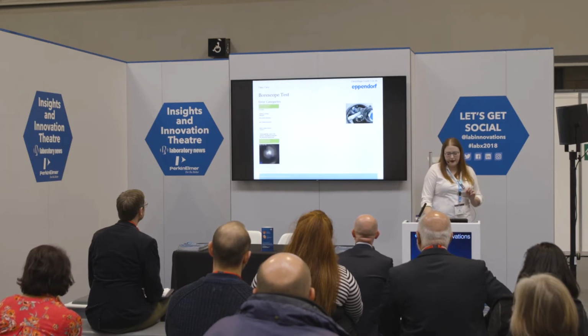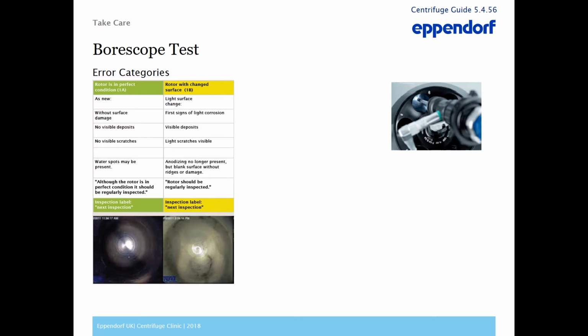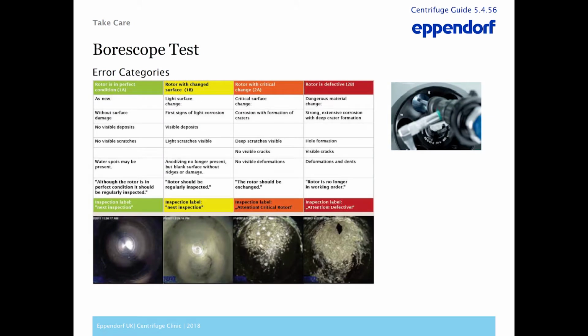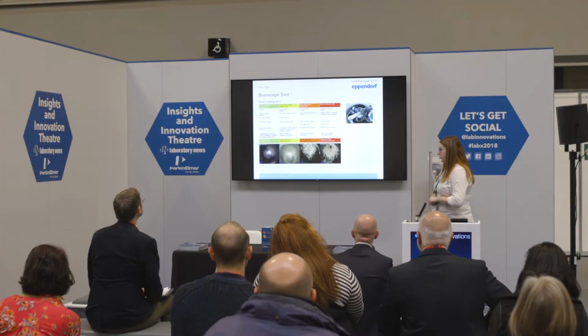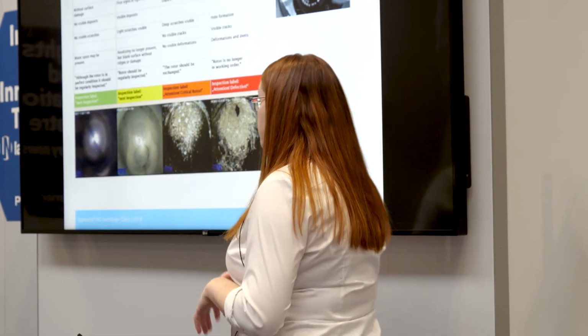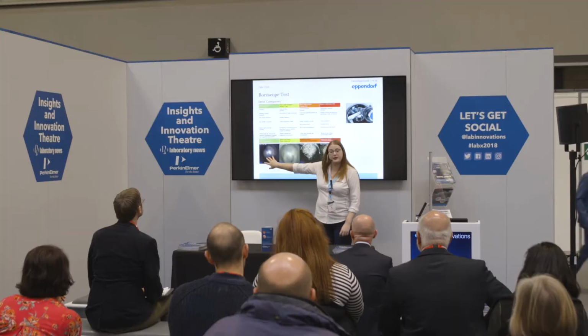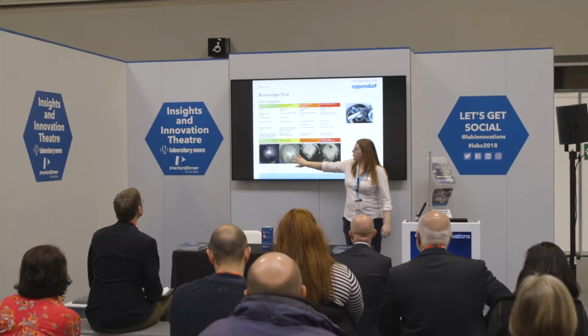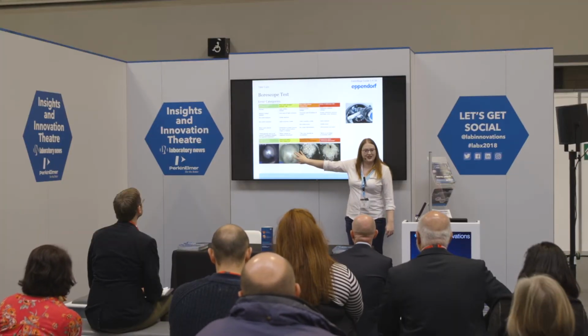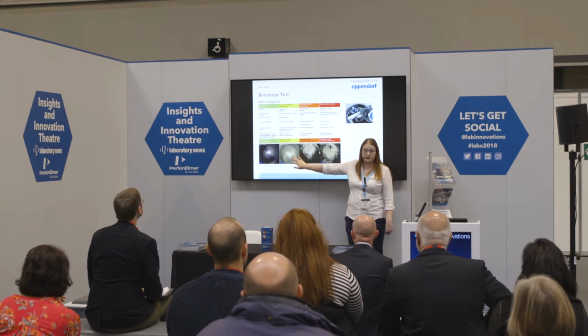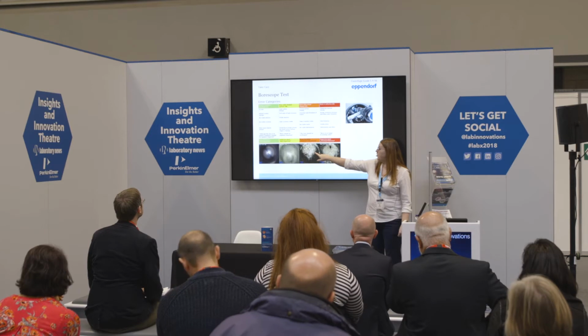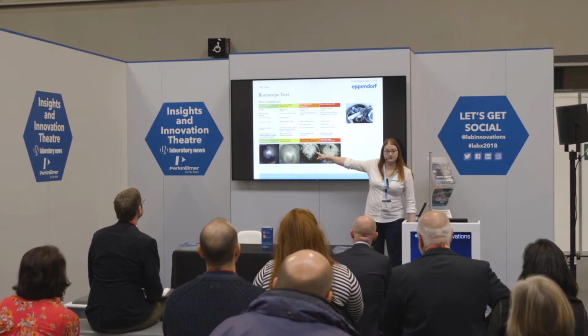When we do our preventative maintenance, we offer boroscope tests. This is basically a camera that goes into your rotor, and we categorize your rotor boreholes based on this system. This is what a new one looks like - great. This is what a used centrifuge tends to look like - also fine, safe to use, but we'll check up on it every time we do an inspection. At this point, we'd tell you to buy a new one.